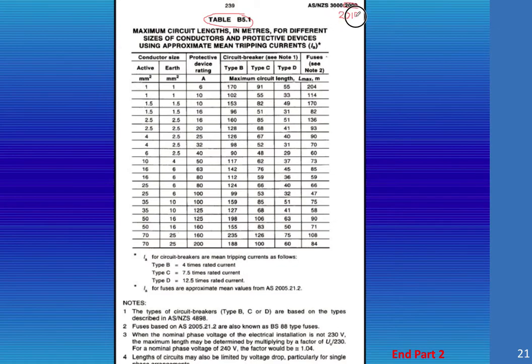We have our active and earths or our conductor sizes, our protective device rating as I should say, and then our circuit breaker types here. And here's the note. We should take note that a B curve needs four times rated load to trip immediately, 7.5 for a C and 12.5 times for a D. The types of circuit breakers B, C or D are based on the types described in the Australian standard for circuit breakers.